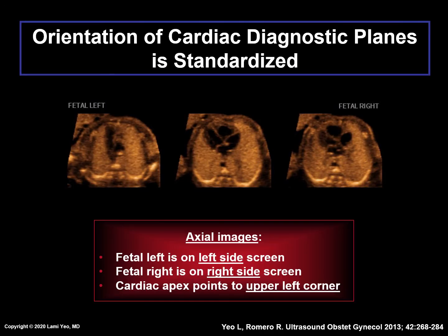We have designed the FINE method so that the orientation of cardiac diagnostic planes is always standardized. This occurs for axial images in which the fetal left is on the left side of the screen. This is indicated by automatic labeling. And the fetal right is on the right side of the screen, also indicated by automatic labeling. Moreover, FINE will place the cardiac apex so that it is pointing to the upper left corner.